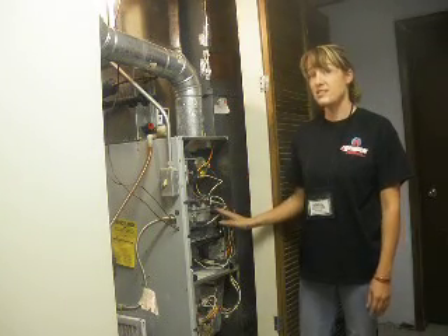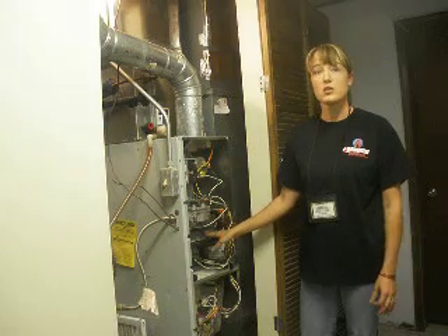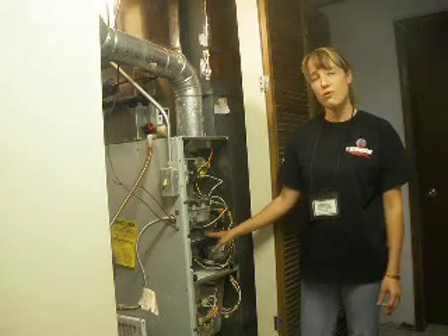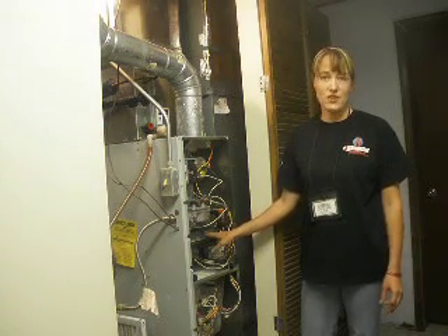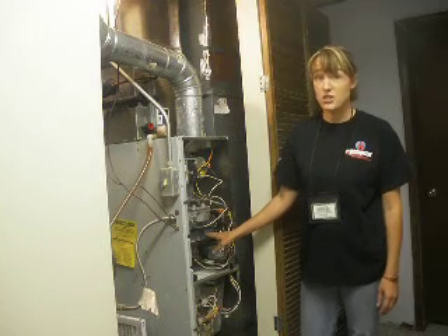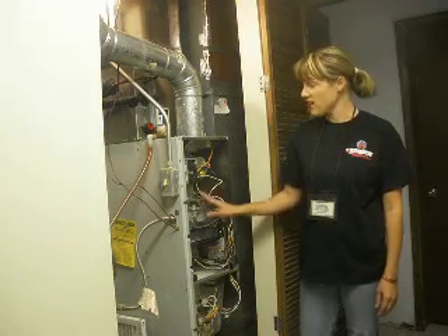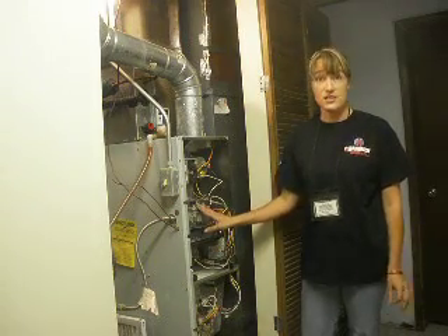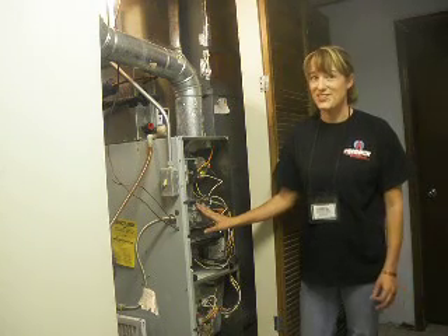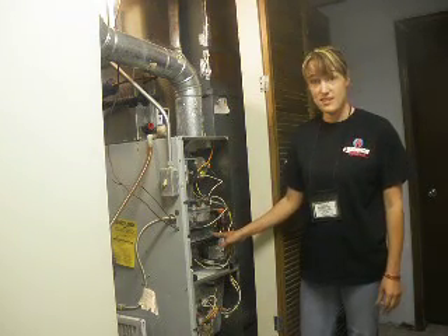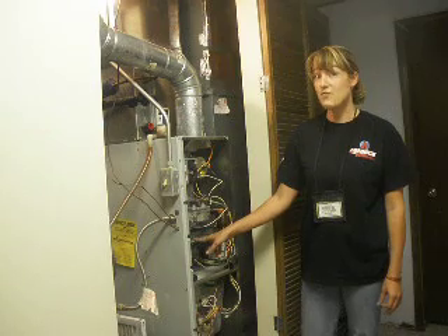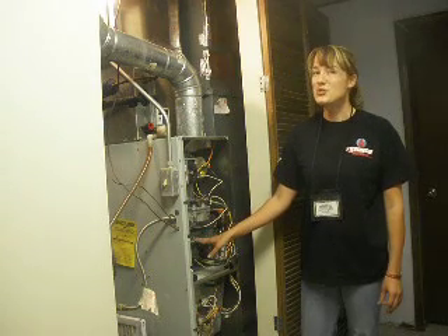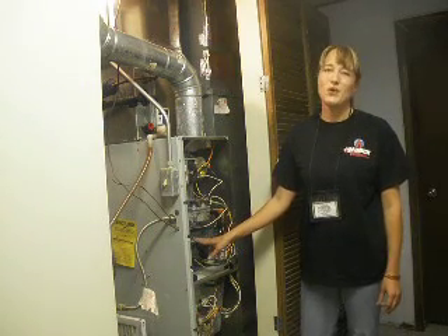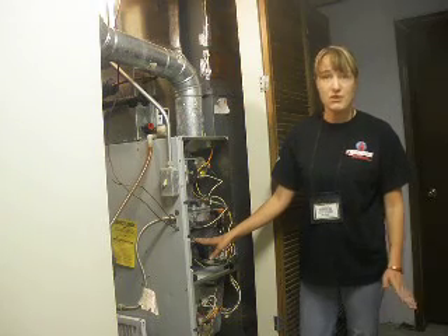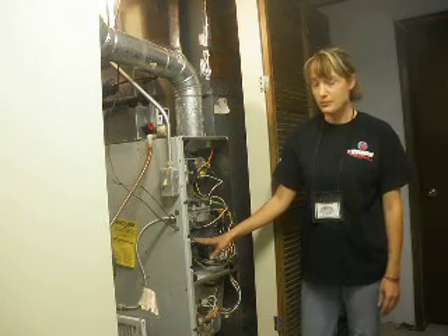Within about 30 seconds, the hot surface igniter is going to begin to glow, reaching approximately 1200 degrees Fahrenheit. An integrated circuit is going to communicate with the gas valve, energizing it. Then we should have ignition, starting at this end, moving across the flame spreader to the flame sensor, which recognizes the flame, allowing the furnace to continue through its cycle.